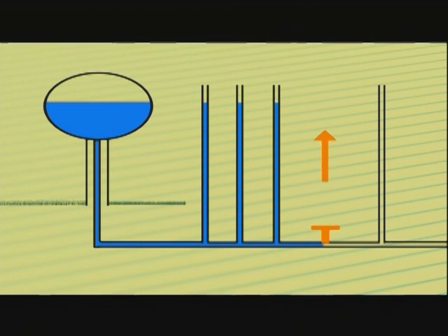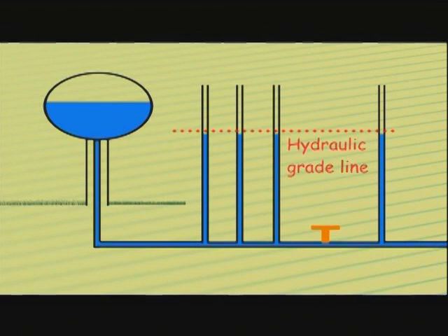Once you open the valve though, the pressure depends on what is downstream. This red line is called a hydraulic grade line. Generally, we use feet with tanks and convert to psi. The result is going to tell you, based on the flow through the pipelines, how much pressure you have at any given point in your distribution system.